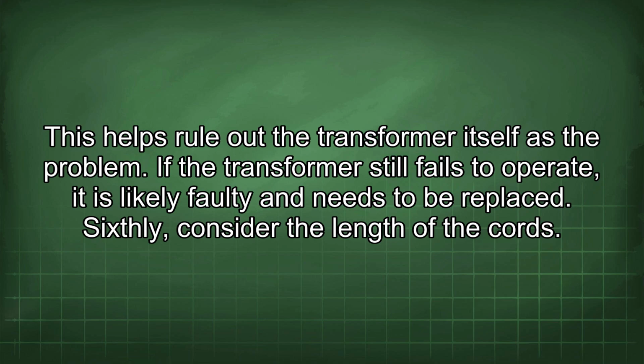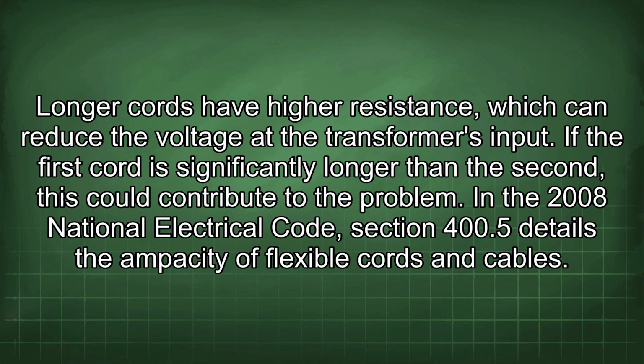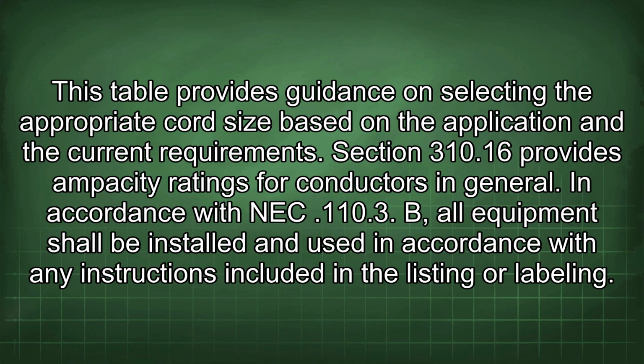Sixthly, consider the length of the cords. Longer cords have higher resistance, which can reduce the voltage at the transformer's input. If the first cord is significantly longer than the second, this could contribute to the problem. In the 2008 National Electrical Code, Section 400.5 details the ampacity of flexible cords and cables. This table provides guidance on selecting the appropriate cord size based on the application and the current requirements. Section 310.16 provides ampacity ratings for conductors in general.